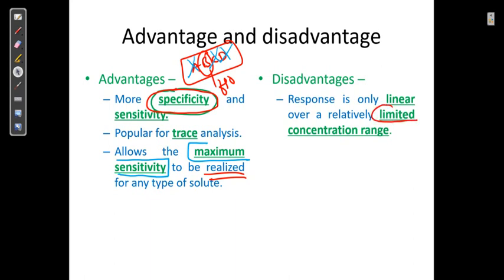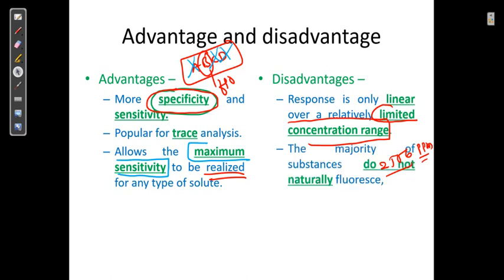The disadvantages of the fluorescence detector: the response is linear only over a relatively limited concentration range. Also, the majority of compounds are not naturally fluorescent, which is a significant limitation for HPLC detector use.